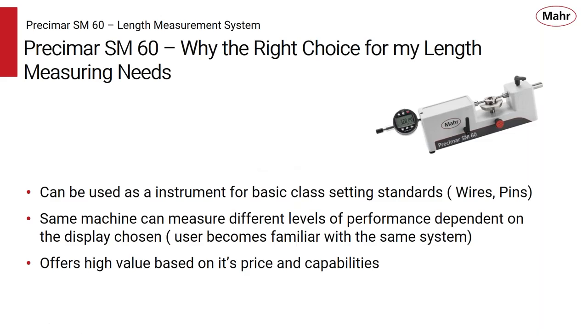You can use the SM60 as an instrument to measure basic class setting standards like wires and pins and so forth. With the 5 millionth resolution, we're in that neighborhood where we can start measuring those types of products. You get everything certified, you have a system capable of doing that. The same machine can be used at different levels of performance depending on the display chosen. So you can have an amplifier on one measuring system for a very high precision application, or you can put a digital indicator on another application somewhere else in the factory, but the operator can still walk up, is familiar with that machine, and is ready to go making measurements. And I think it offers high value based on its price point and capabilities.